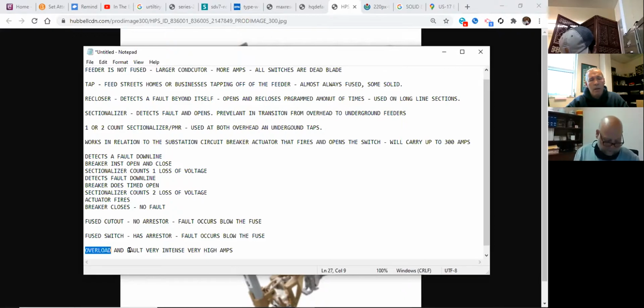In a fault condition, the fuse will be destroyed. All you'll have is a little piece of wire rope, and the rest of what's inside the tube will pretty much be gone. So that's a good indicator right there: when you take that cap off the end of the fuse barrel and you take the fuse out, if most of the fuse is still there and you see the melted tips of the connection come out with the wire rope, that fuse has been melted. You just had an overload. If you start taking the wire rope out of the fuse barrel and then take the cap off and take the other end off, there's nothing left. It's just burned up. So that's a good detection method of finding out if you've either had an overload or a fault when you come to an open switch.